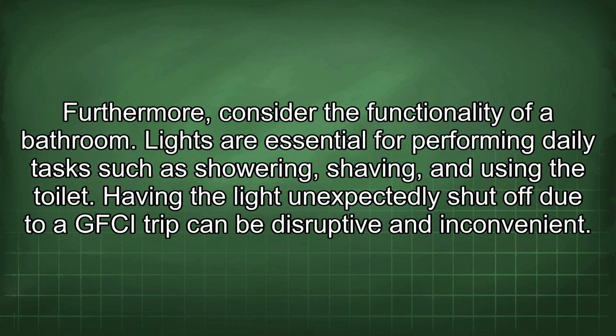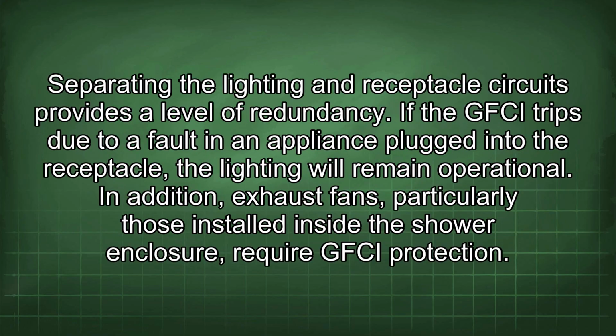Furthermore, consider the functionality of a bathroom. Lights are essential for performing daily tasks such as showering, shaving, and using the toilet. Having the light unexpectedly shut off due to a GFCI trip can be disruptive and inconvenient. Separating the lighting and receptacle circuits provides a level of redundancy. If the GFCI trips due to a fault in an appliance plugged into the receptacle, the lighting will remain operational.